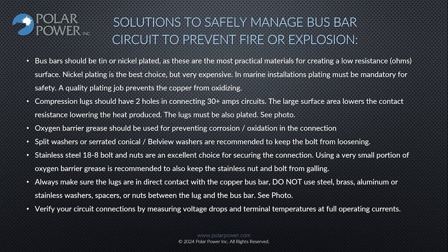Compression lugs should have 2 holes in connecting 30+ amp circuits. The large surface area lowers the contact resistance, lowering the heat produced. The lugs must also be plated. See photo. Oxygen barrier grease should be used for preventing corrosion and oxidation in the connection. Split washers or serrated conical or Belleville washers are recommended to keep the bolt from loosening. Stainless steel 18-8 bolts and nuts are an excellent choice for securing the connection. Using a very small portion of oxygen barrier grease is recommended to also keep the stainless nut and bolt from galling.